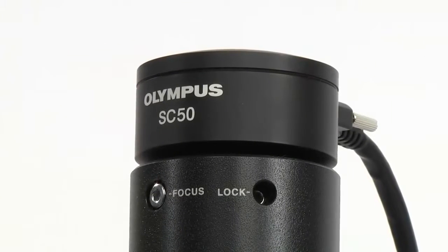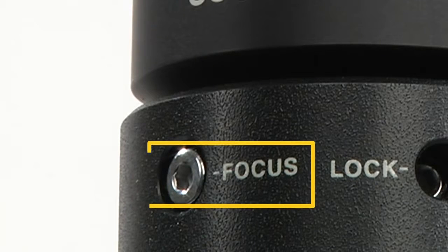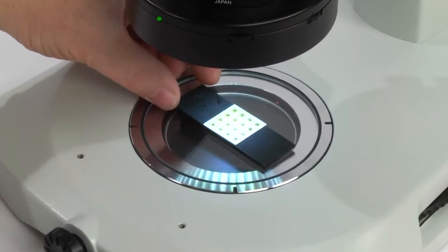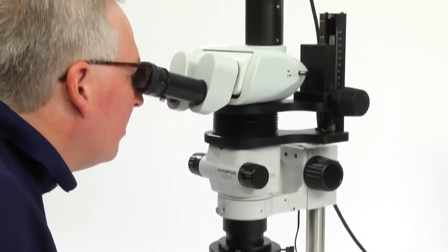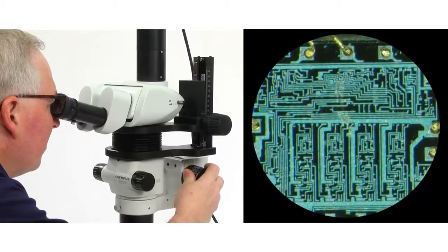For this procedure to work, the microscope should be equipped with a camera mount that has a built-in focus adjustment. First, place a sample on the stage plate. While looking through the eyepieces, bring the image into focus using the microscope focus knob.